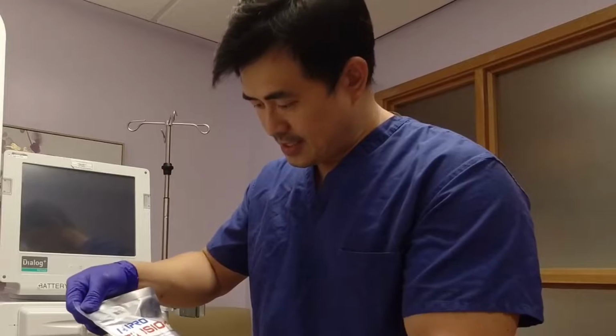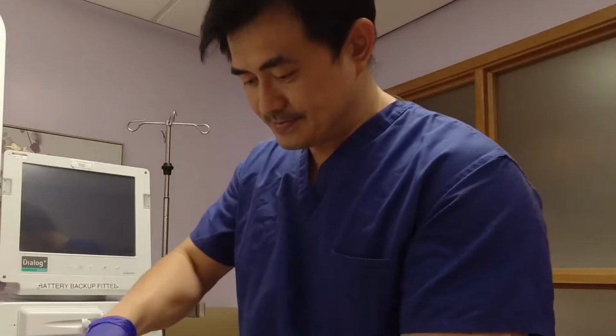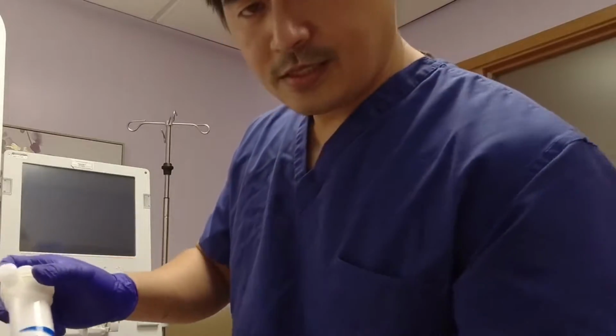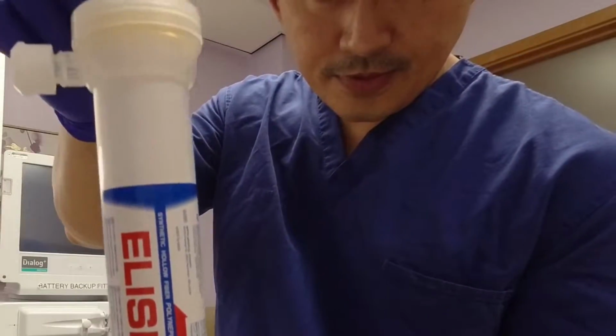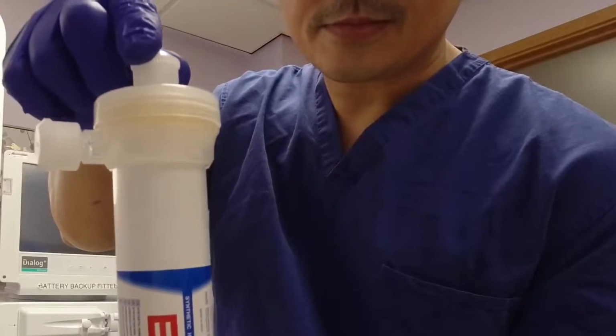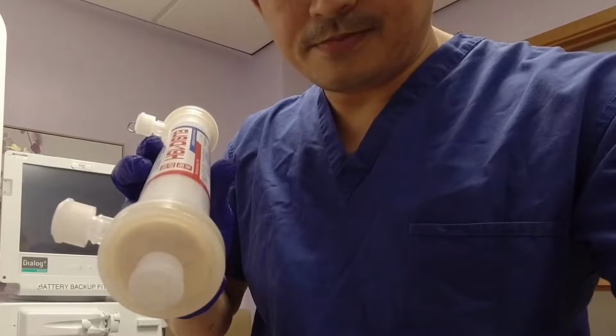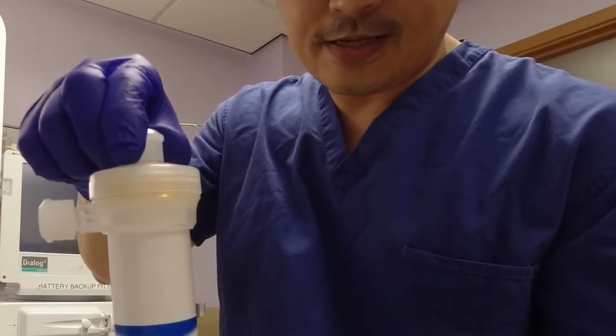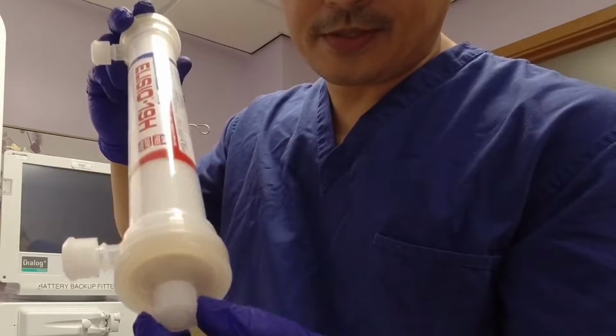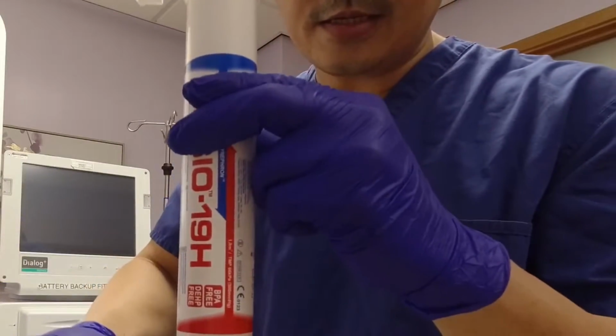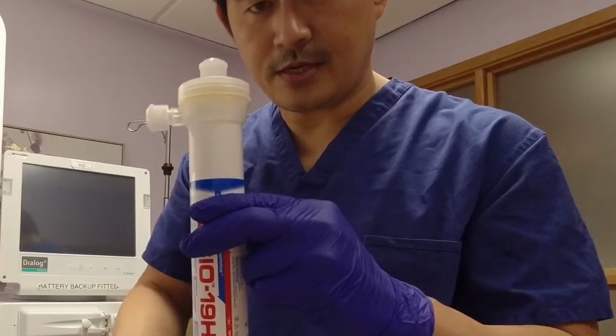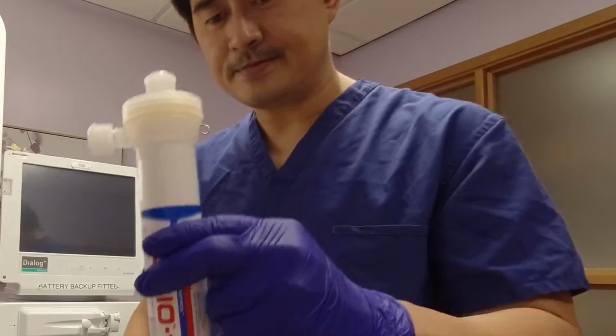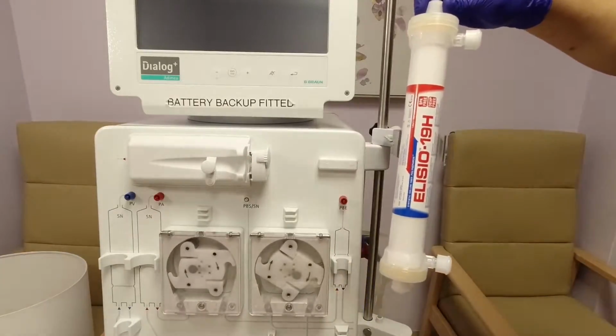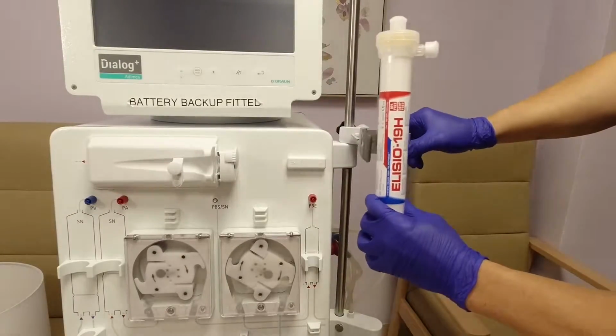Right, so basically we're gonna start by putting our dialyzer. So this is how a dialyzer looks like. There you are. So this is your artificial kidney. You got two ports in there, one on the top, one at the bottom. You got one for the arterial port and you got one for the venous port. And same thing, as you can see on the side, that's where your dialyzer coupling goes. One for arterial and one for venous. So your dialyzer goes into your dialyzer holder.